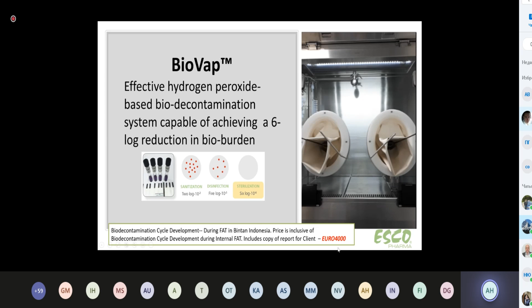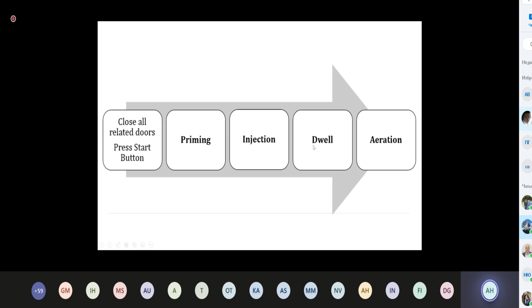Okay. The process is simple. You pass your pressure testing, close all the door, start your pressure testing, pass, then you inject the gas. You keep the gas constant. You stay there. It's called dwell. And then you remove the gas. That's called aeration. Okay, then this here will be the menu for biodecontamination. You can have a master decontamination where you decontaminate the whole isolator, or you can decontaminate individual chamber, process or the main chamber, or the pass-through chamber. You can select which chamber that you want.